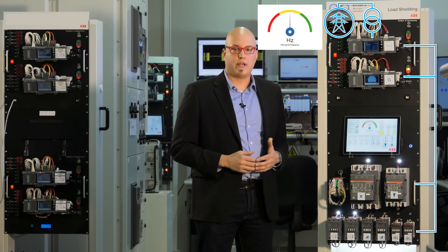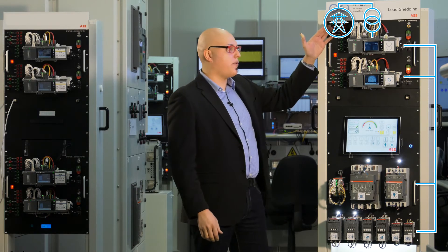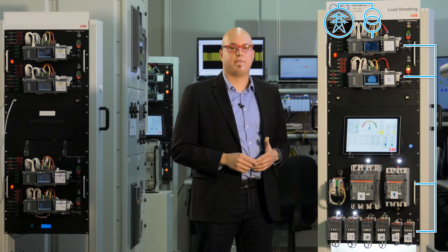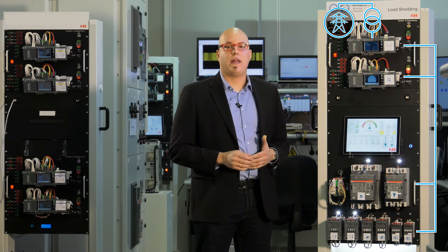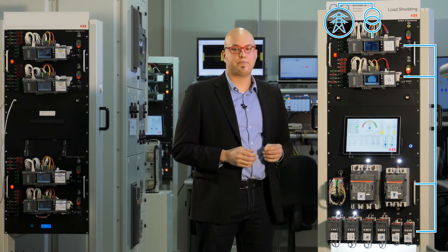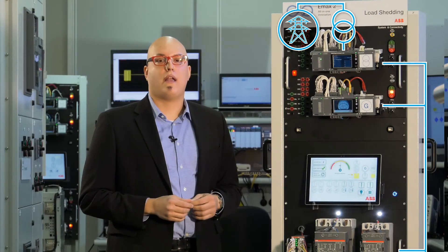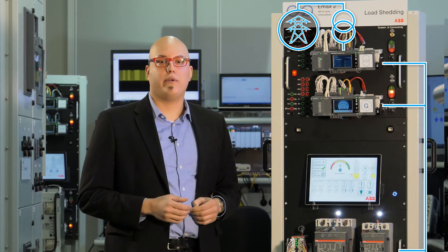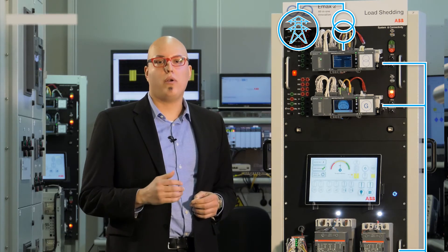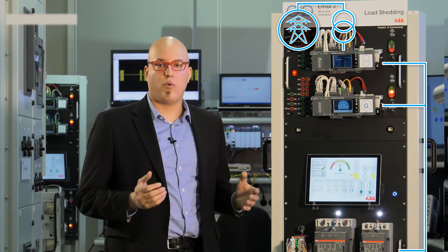Emax2 understands the power to be shed. It measures the power flowing from the medium voltage to low voltage transformer and estimates the photovoltaic production, even if there are anti-islanding protections at the solar inverters. It knows the priority and the power for each non-critical load, so as to adapt the load shedding only to the amount required.